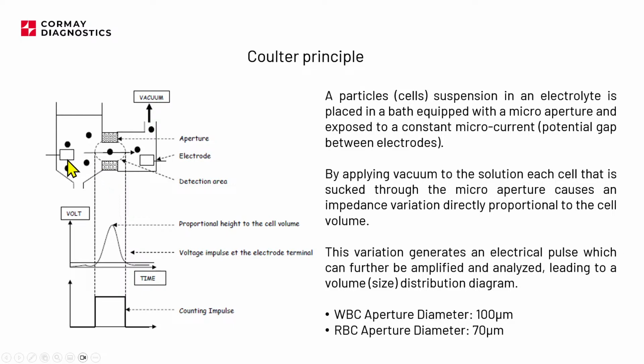So what is happening? On one side of the aperture, we have the chamber, right, where we are making the dilution, and there is one electrode. The aperture itself is not conductive, so it will not conduct any electricity. The only path for the current is through the liquid which is in the aperture, and the aperture size is quite small. It's a small opening, a small hole, and on the other side we have a second electrode. So let's apply a constant current across those two points. When we measure the voltage, we will have a voltage which is at one level, because the size of the aperture is constant, right?